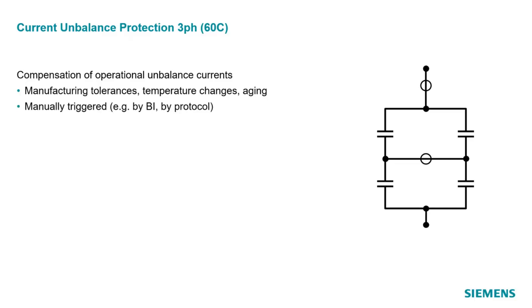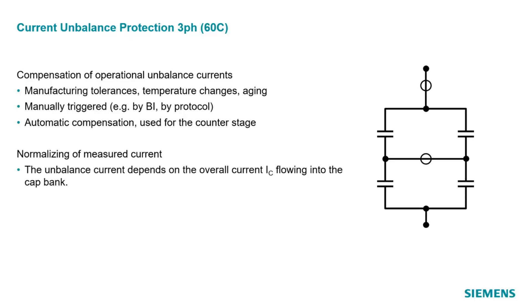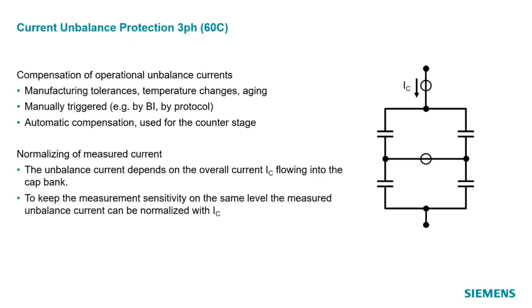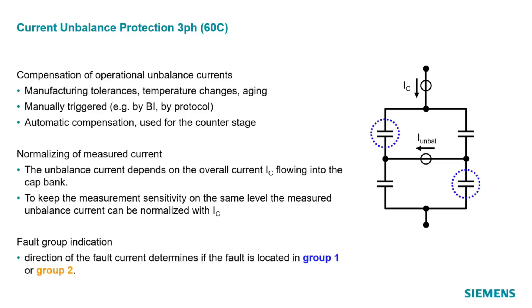The compensation can be performed manually, triggered by a binary input or via protocol, or automatically. In the automatic case, every slowly occurring unbalanced current will be slowly subtracted from the measured current. For the counter stage, the automatic compensation is mandatory. Regarding normalization of measured currents: the unbalanced current depends on the overall current IC flowing into the capacitor bank. To keep the measurement sensitivity at the same level, the measured unbalanced current can be normalized with IC. The direction of the unbalanced current allows finding the location of the faulty element — it can be assigned to group one or group two.